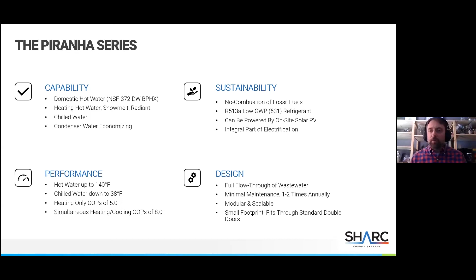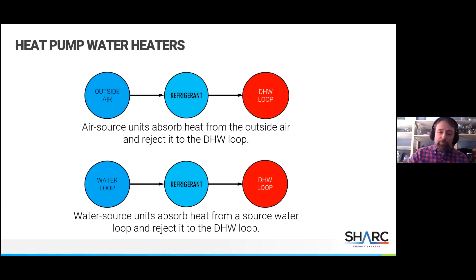Kind of going back to the heat pump water heater, breaking it down even more. There's two different types of heat pump water heaters out there: air source and water source. One is taking heat from the outside air, transferring it to that refrigerant, and then transferring it to your domestic hot water loop. The second type is taking that heat from a water loop, usually condenser water, and transferring it to that refrigerant and then onto your domestic hot water loop. So again, very similar in concept.